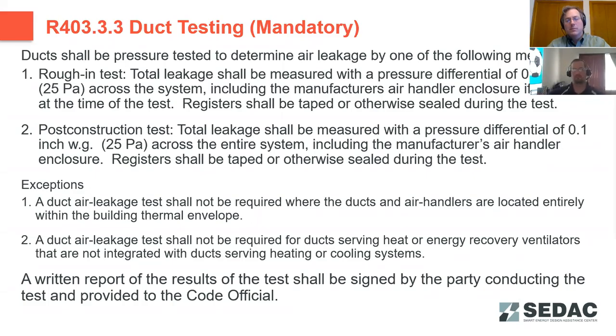If ductwork is all entirely within the thermal envelope of the house, then you do not have to do pressure testing because any leaks, again, are inside the conditioned area of the house and assumed to condition that space. Also, duct testing is not required on ducts that serve energy recovery systems. So if you've got an HRV hooked up to your furnace, those connecting ducts do not need to be tested for leakage. A written report of those test results does need to be included and provided to the code official. And it's also included on the certificate that is included, the compliance certificate for the house.